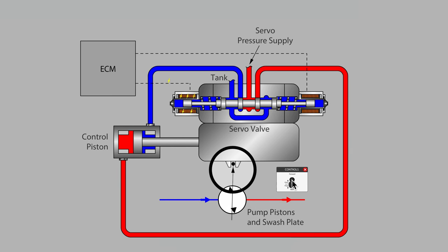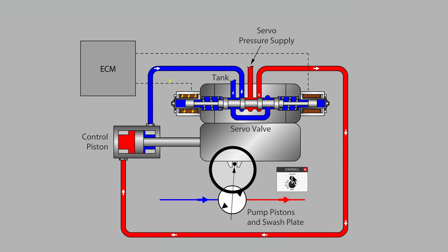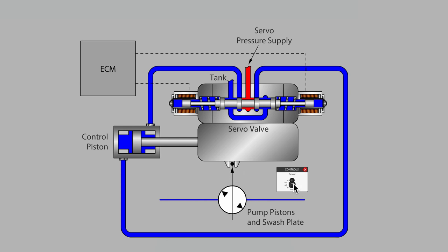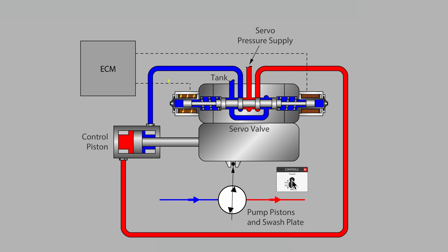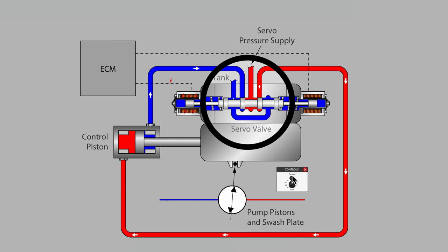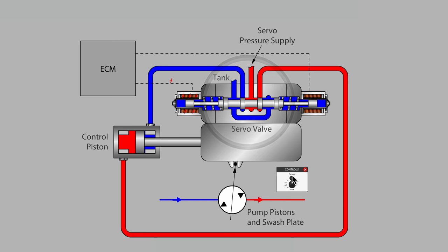As the control piston moves the swashplate, it also moves the valve body to catch up with the internal valve spool position. As the valve body catches up with the spool, the valve closes and the control piston motion ceases.